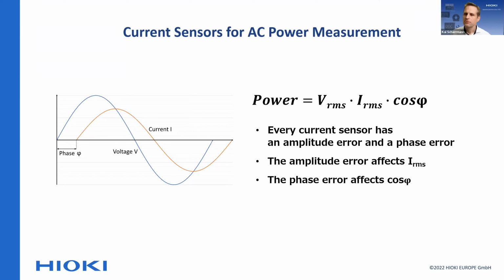So we've got the amplitude error and the phase error. Looking at the calculation of AC power, that's voltage times current times the power factor, which is cosine phi. In that formula, you have the current I and the power factor, cosine phi. The amplitude error you see in specifications for current sensors affects the I, while the phase error affects the power factor, the cosine phi.